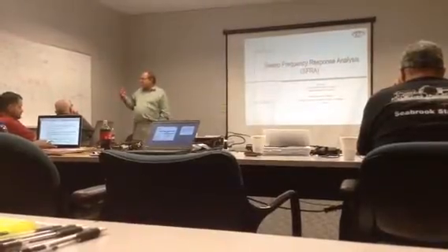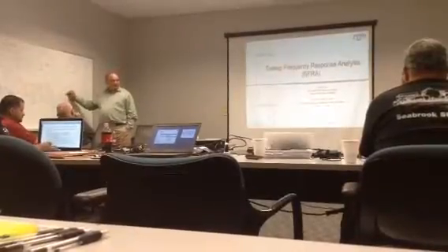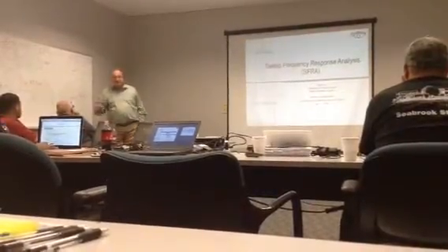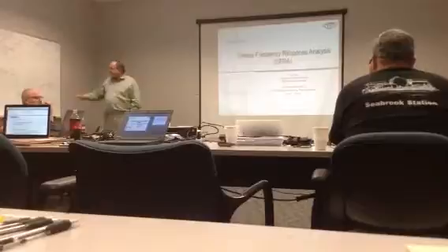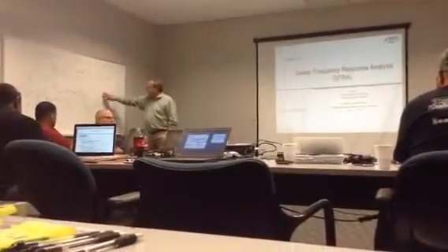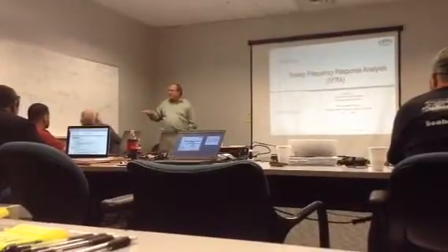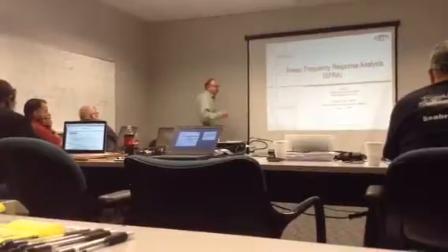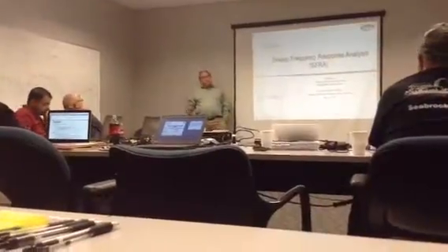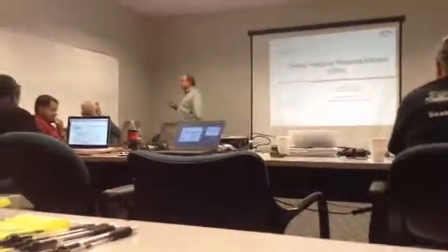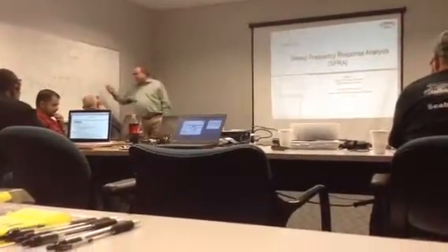But this is almost like what they call signature analysis too. That a healthy unit is going to look like this. And if there's been a change of some sort, a physical change, it's going to look different. It might look different here, it might look different here, it might look different here. But what we are looking for here is, and it's like what we talked about with capacitance, and if you ever look at leakage reactance and whatever, is a physical change.